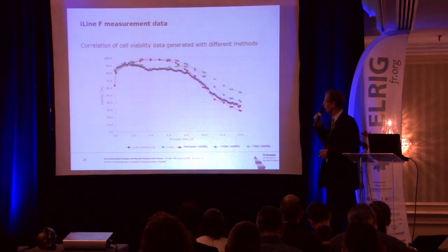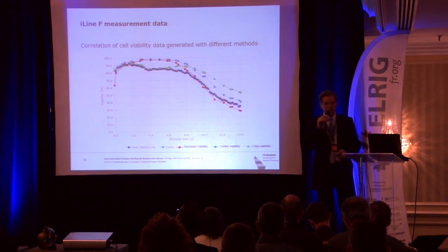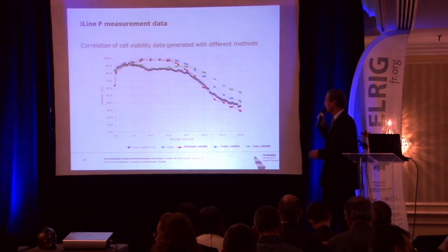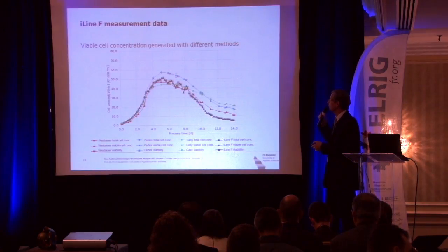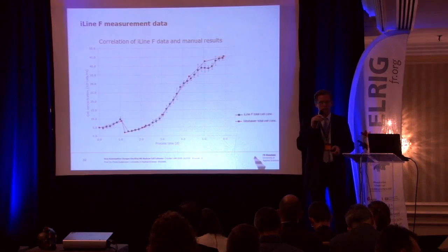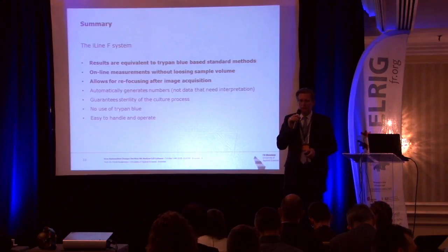results you get, the results are here, the dots, the results are in line with manual cell counting or the technologies that are based on image recognition, like here the CEDEX system or the Beckman Coulter Vi-CELL system. And you get a big amount of data. Every half an hour you are able to record one data point. And that is also true not only for the viability, but also for the cell concentration. Here another batch just to prove that this is true. So results are equivalent.